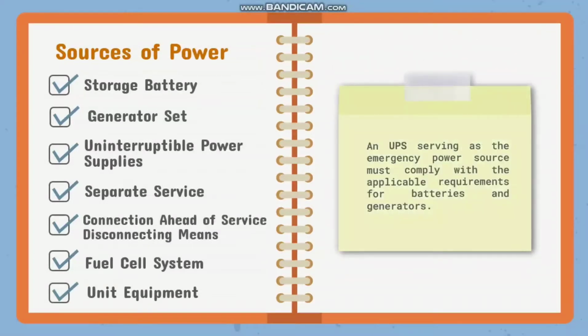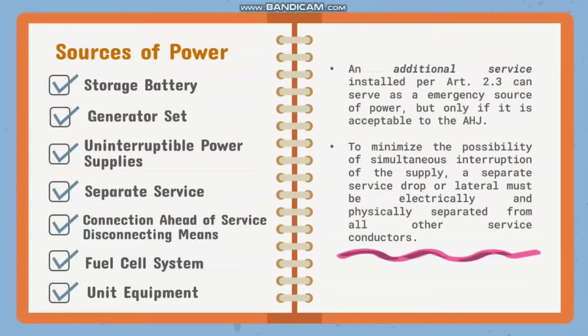So next, for the uninterruptible power supplies, a UPS serving as the emergency power source must comply with the applicable requirements for batteries and generators. An additional service installed per Article 230 can serve as an emergency source of power, but only if it is acceptable to authorities having jurisdiction. So to minimize the possibility of simultaneous interruption of the supply, a separate service drop or lateral must be electrically and physically separated from all other service conductors.